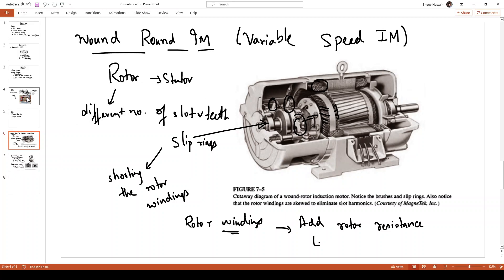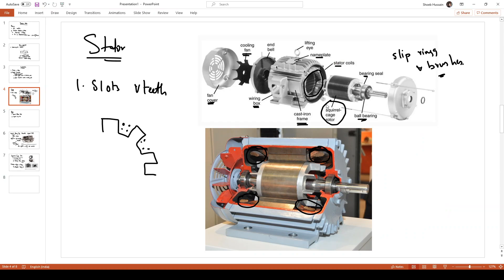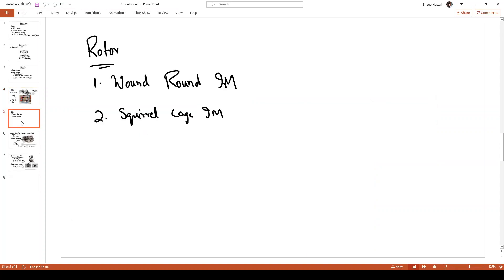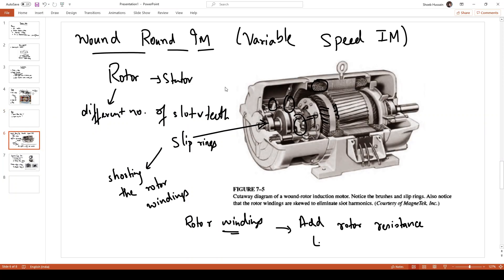These are the constructional details of induction motors. The principal parts are the stator and the rotor. The stator provides the field circuit and using its windings we can produce an n-pole structure for the induction motor. The second principal component is the rotor, which comes in two structures: the wound rotor and the squirrel cage. In the wound rotor induction motor, the rotor has slots and teeth and also carries rotor windings.